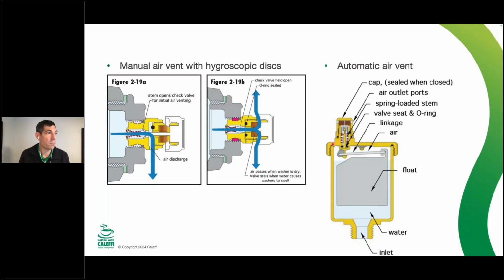An automatic air vent may still have those little fiber washers. This is an accessory that works with our air vents as well as other competitors most of the time, because it seems to be a similar thread on the top that should be the same across a lot of different brands. So an automatic air vent is a little bit different because when air comes up to the top here, it's going to allow that float to drop. This is just a little needle valve, like a Schrader valve in a tire or something like that. So as the float drops, the air is going to vent out. As the air is vented out and the float comes back up, then it closes up the needle valve. One thing to pay attention to here, you want this little pocket of air here.